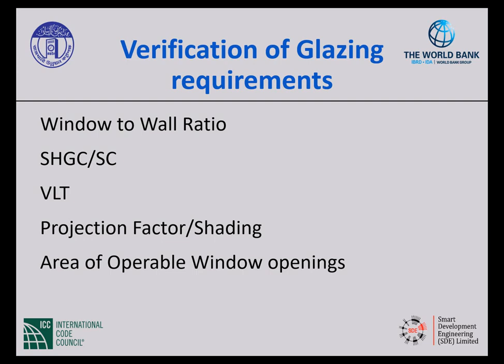So it is important to verify that they've got the right solar heat gain coefficient and the right VLT, especially that SHGC, because that's going to play a huge role in sizing the mechanical equipment. On the amount of windows, are they on the north, south, east, or west, and what solar heat gain coefficient do they have? Because that could be a lot of heat making it into the building, depending on all of those factors. So we really want to verify it in the field.